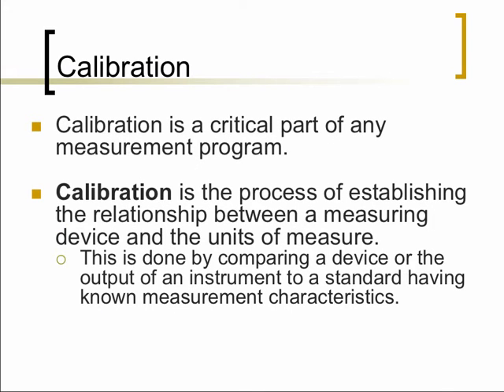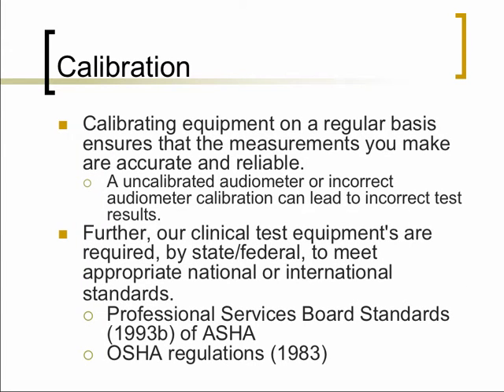And this becomes very important as a clinical audiologist, especially because we depend on the integrity of the instrumentation for us to evaluate our patients' results. So it's essential that the clinician periodically evaluates the internal consistency of the equipment. And as we get used to more sophisticated equipment for testing, there's an increasing demand on audiologists to at least have the knowledge and the skills for the maintenance and calibration of your clinical tools. So calibrating equipment on a regular basis ensures that your measurements are accurate and reliable. And if you have an uncalibrated audiometer, of course, it's going to result in you misdiagnosing.